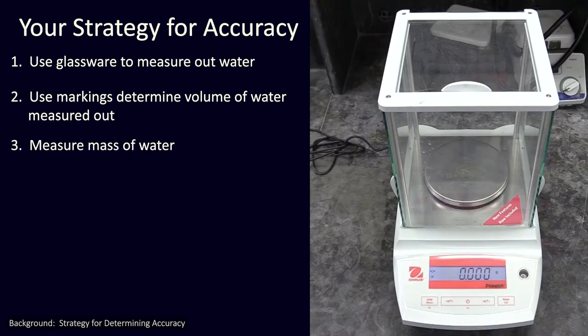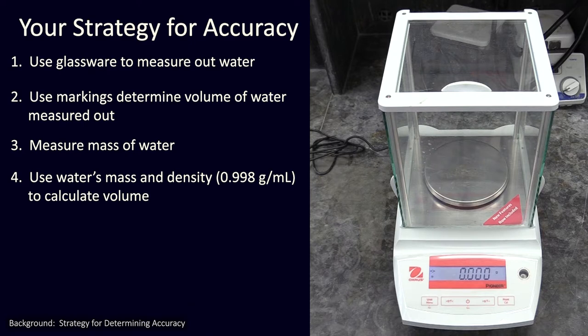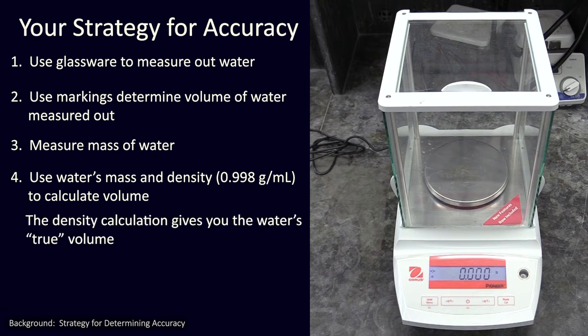You'll then use a scale like this one to measure the mass of the water you dispense, then use the density of water, 0.998 grams per milliliter, to calculate the volume of water you dispensed. Now these scales you'll be working with have been checked and evaluated to give you accurate mass readings, so you can assume the volumes you calculate will be highly accurate. Therefore, you will know the actual true volumes of water you measure out.